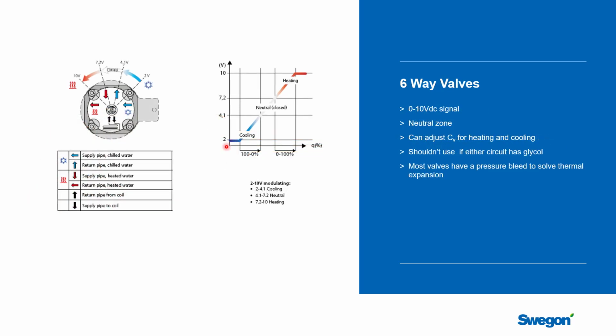A little bit more detail about how the valves work themselves. Imagine you have a control valve that's modulating with a 0 to 10 volt signal, so you can get a sense of what's going to go on here. Between 2 and 4.1 volts, you're going to get the cooling performance, and so that's this part here. So as the voltage signal goes up, this unit will increase the amount of chilled water flow.